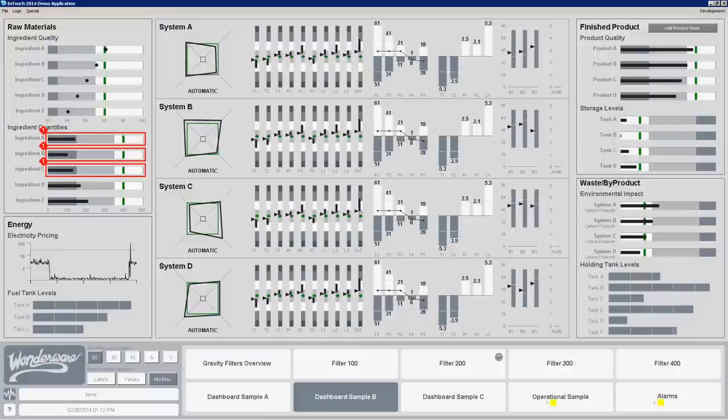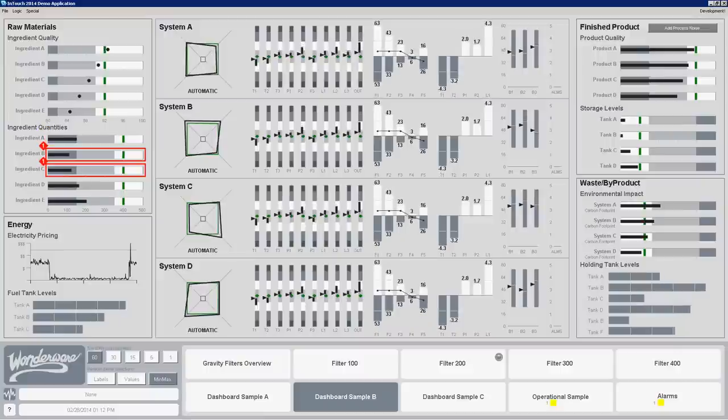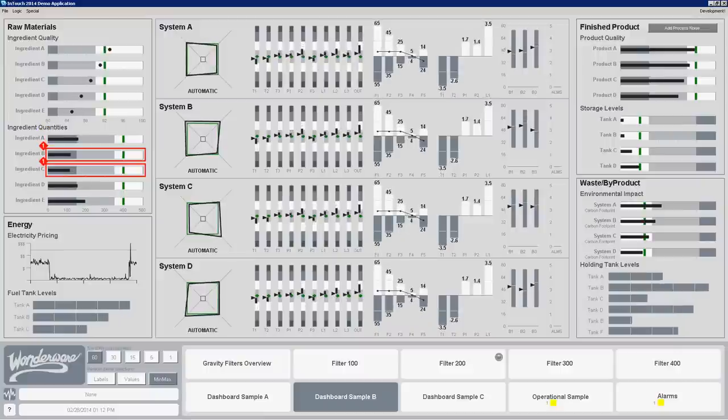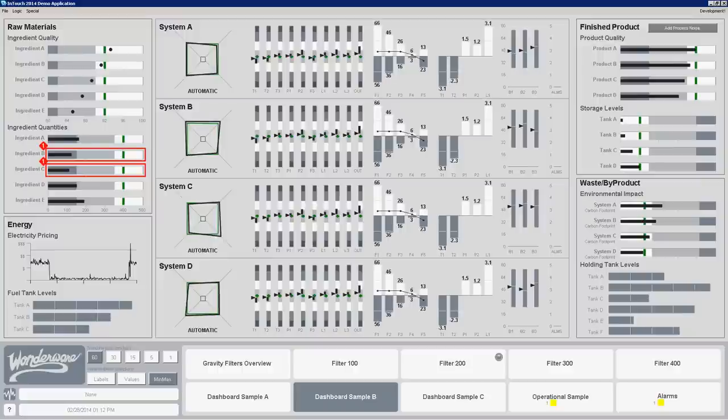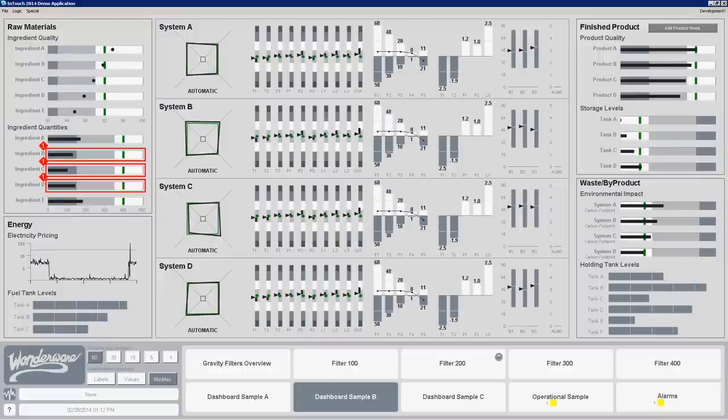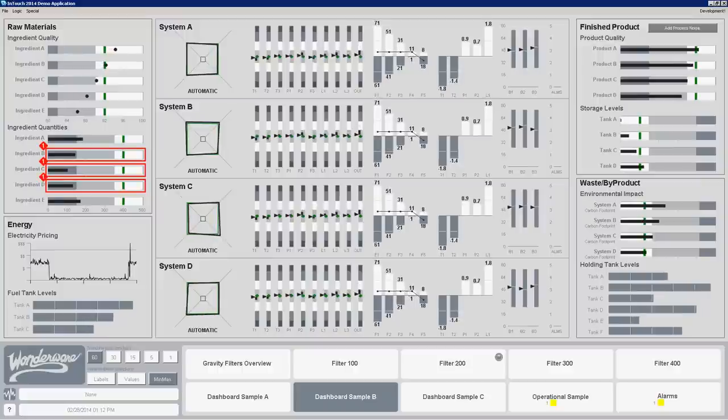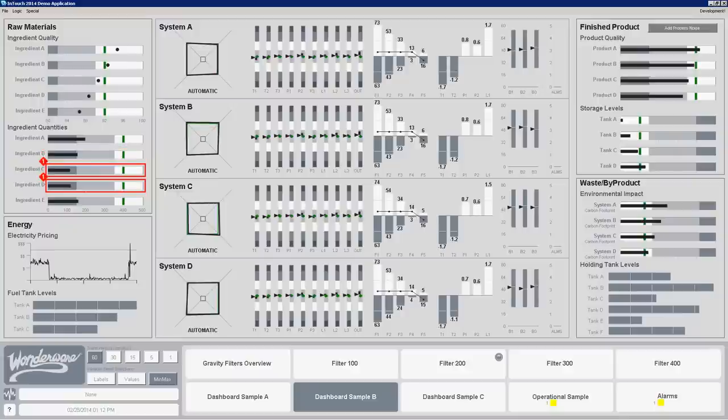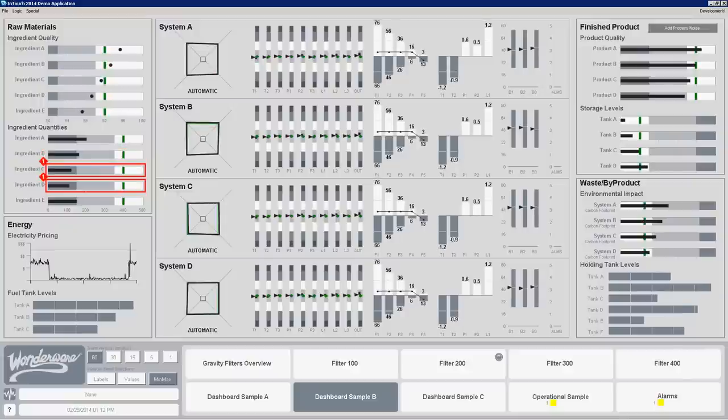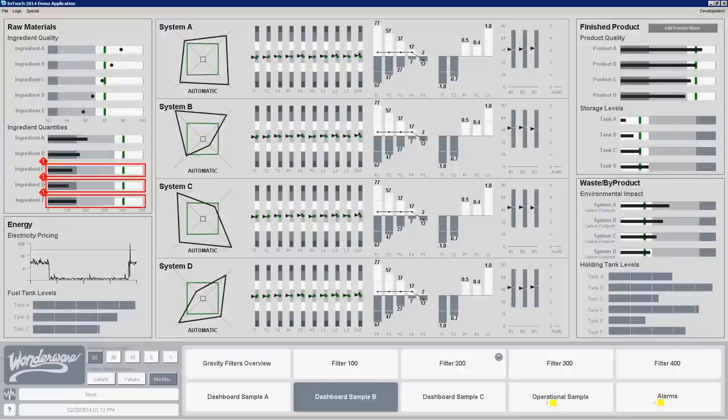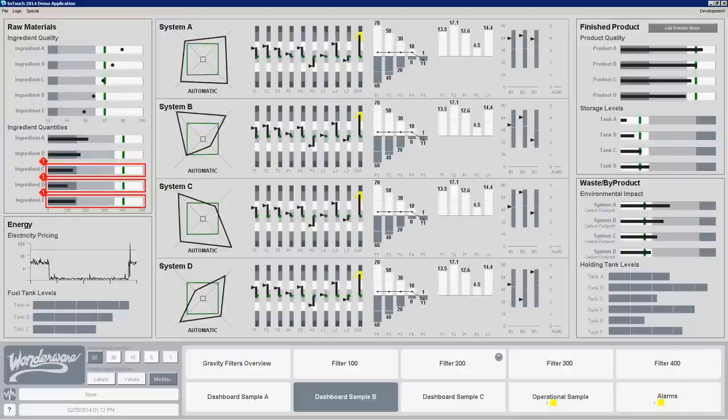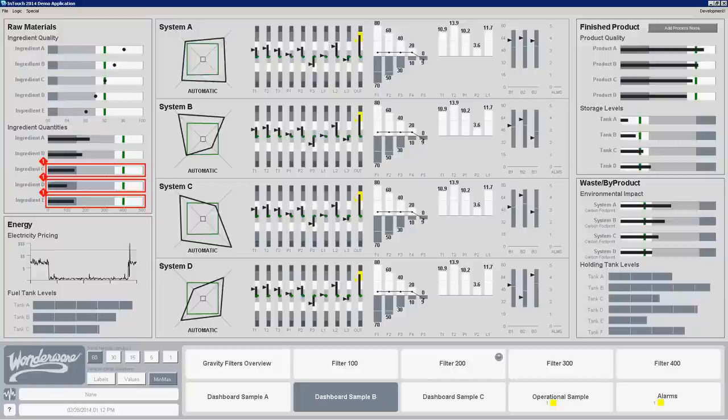The more contemporary ways of building HMIs are talking about a hierarchical organization of your windows into four levels. The first level we'll talk about today is level one. The level one windows are really intended to provide you a wide overview of the system and provide at a glance awareness of where there is action that needs to be taken.